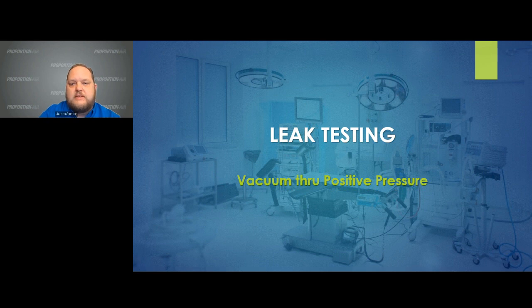One of several leak test examples we have in the medical manufacturing environment is leak testing IV bags. This same principle can apply to any leak test where the item needs to be filled and then fully exhausted of the fluid. In this example, we use a QB3 pressure regulator to test an IV bag for leaks. The QB3 is an ideal choice for the application because it negates the need to use 2 separate devices. With many manufacturers, you'd need a device for positive pressure and one for vacuum. The QB3 handles that all in one unit. Let's see how this works.